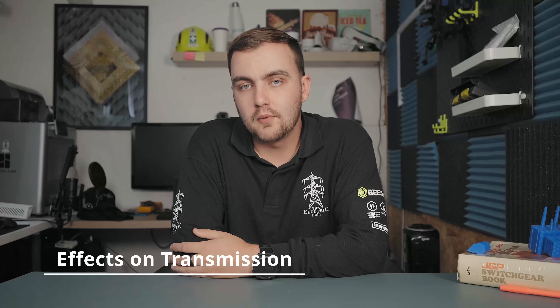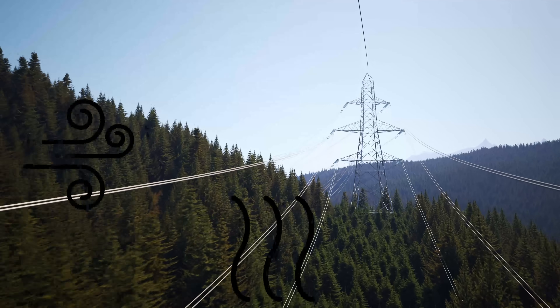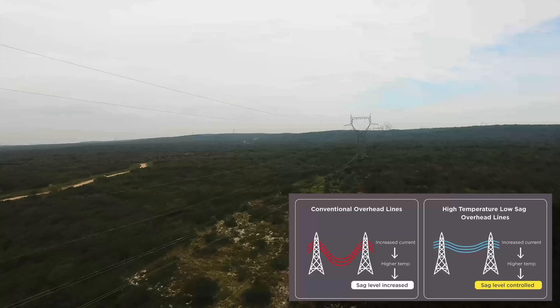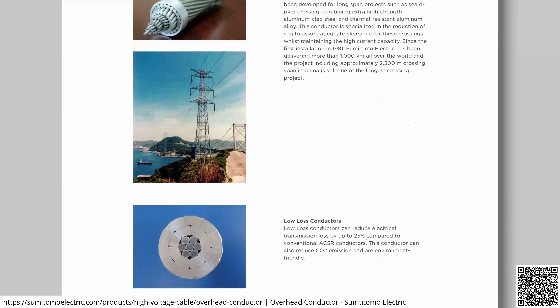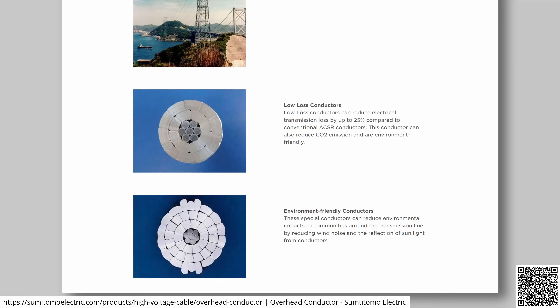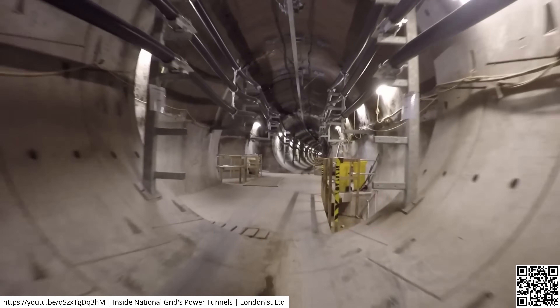Transmission is also affected by the heat. Hot weather reduces the capacity of overhead lines, as the air provides natural cooling for them, and hotter weather means less cooling. Most overhead lines are made from steel, aluminium, or a combination of materials that cause them to expand when heated and then sag. The sag of a line is carefully calculated so under load it doesn't sag too much and end up zapping something, starting wildfires, or hurting someone. There are new high temperature low sag conductors available, which are composite materials and can run hotter because they don't expand so much with the heat. This allows higher power flows, but they're uncommon on the grid at the moment. We also use dynamic line rating to measure the temperature in real time, so we can dynamically alter power flows to minimise sag.